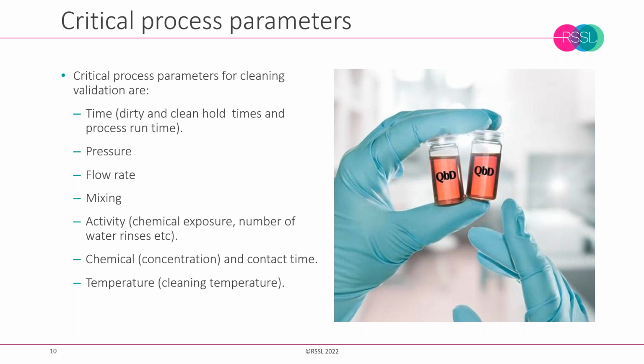There's also going to be temperature, because the level of cleanliness we can achieve is going to be proportionate to the temperature at which we're running the cleaning process. And generally, the lower the temperature, the less effective that becomes. There's also going to be the concentration of cleaning agents. And we also need to have in control things like ensuring that surfaces are still in the validated state. So if we get excessive roughness of surfaces, then we end up with surfaces that are more difficult to clean. And we also need to control flow rate and any mixing requirements.